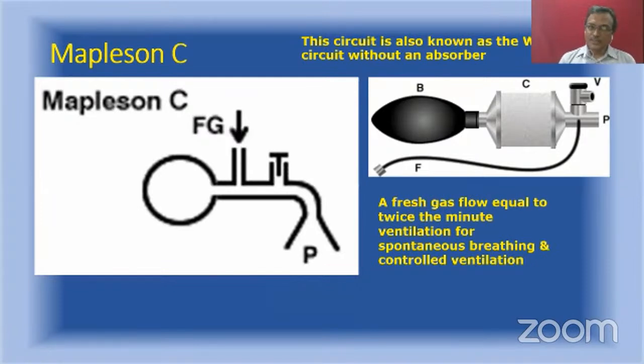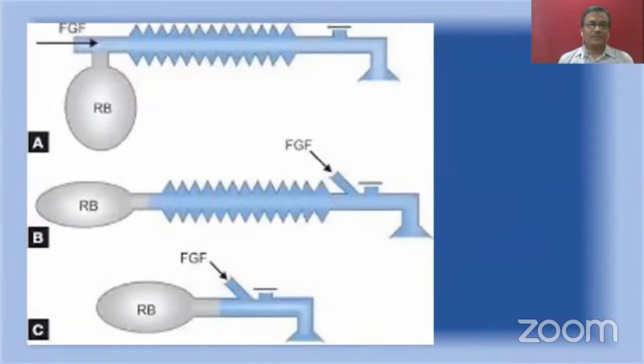And fresh gas flow, as in the case of Mapleson B, is twice minute ventilation for both spontaneous breathing and for controlled ventilation. So far we have discussed Mapleson A, B, and C. Let us just compare and contrast. I said always think in terms of anatomy and physiology. Okay, let us consider the anatomy. Of course, in all circuits, the APL valve is close to the patient. Okay, and in the A circuit, fresh gas flow is away, but in B and C, it is just behind the APL valve. Second difference. Considering the reservoir tube or the corrugated tube, the tubes are there for A and B, but there is no tube for Mapleson C.